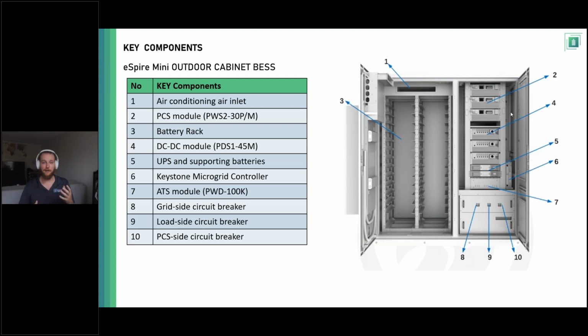In terms of DC coupling, right below those inverter segments, those 45 kW DC to DC modules can each take 45 kW, right? So 45, 90, or 135, depending on how much solar you have. And in addition to this, there's also an ATS in this unit to handle the grid following to grid forming switching. It's about a 30 millisecond transfer time. So while it's not a UPS system, it's not good for critical data center operations or hospital equipment that has to have less than a cycle or a cycle and a half of downtime. This does have relatively quick switching, 30 milliseconds.